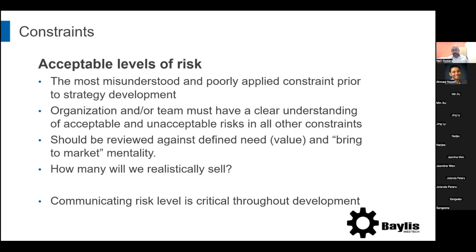What typically happens, and this happens at Baylis too, is there are two different ways people react when they develop a product and they're going through all the V&V and thinking through how the product's going to be used clinically, or doing clinical studies or animal studies, and something comes up: they see all risk as bad and all risk as their own problem, and that it has to be overcome by technology or something. And the reality is that that's not how any medical device out there in the world that's on the market actually was brought to market.